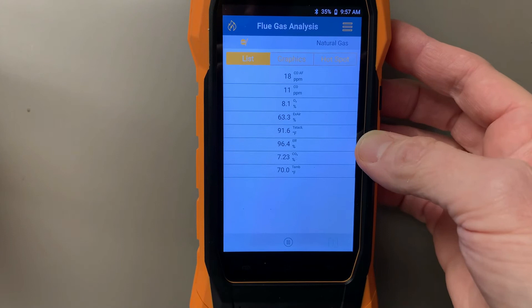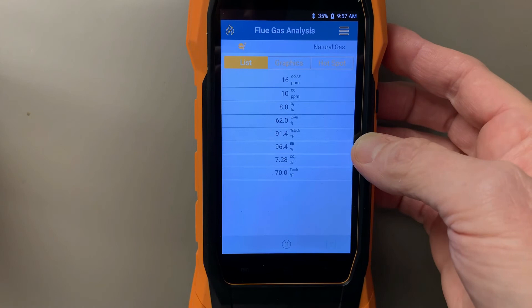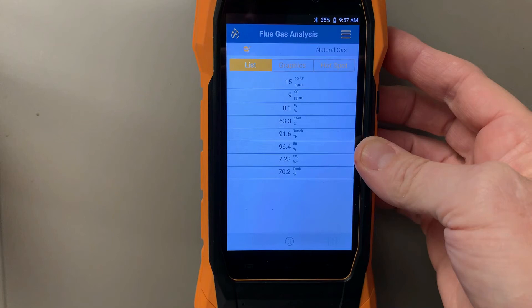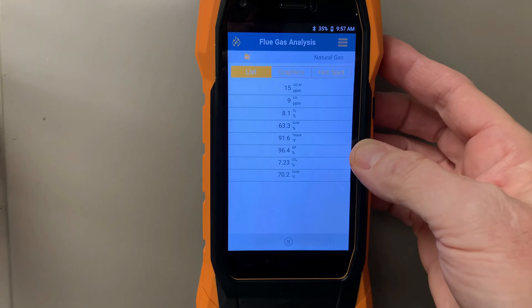The efficiency you see on this meter is not the same thing as the AFUE on the tag of the unit — those don't match up. AFUE is a seasonal number taking into consideration on times, off times, things like that. This efficiency is how well you utilize the fuel. So it's two different numbers — don't look to try to match those up. Sometimes they match up and it makes you feel good, but it doesn't really change anything.